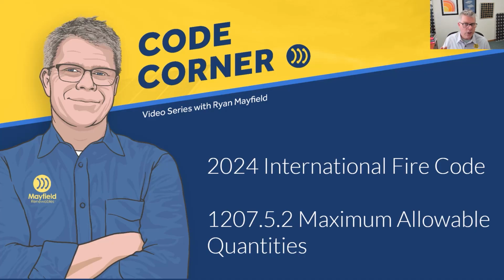1207.5.2 is the specific section that we're talking about, and maximum allowable quantities is referring to the amount of energy storage we can have in specific locations. Quantities being the kilowatt hours, that's how we're going to measure these, and we're just setting up these maximum values that we can have. It's really about safety for firefighters and trying to keep the locations as safe as possible in regards to the amount of storage capacity that we have.